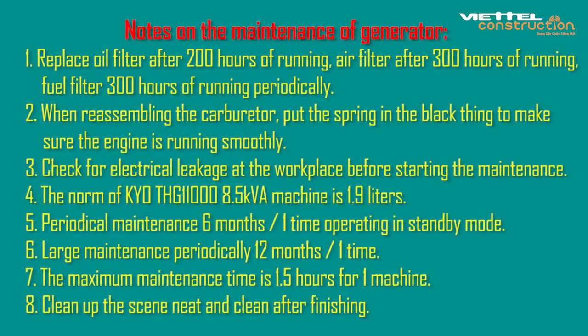Notes on the maintenance of generator. 1. Replace oil filter after 200 hours of running, air filter after 300 hours of running, fuel filter 300 hours of running periodically. 2. When reassembling the carburetor, put the spring in the black thing to make sure the engine is running smoothly. 3. Check for electrical leakage at the workplace before starting the maintenance. 4. The norm of KYO THG11000 8.5kVA machine is 1.9 liters.